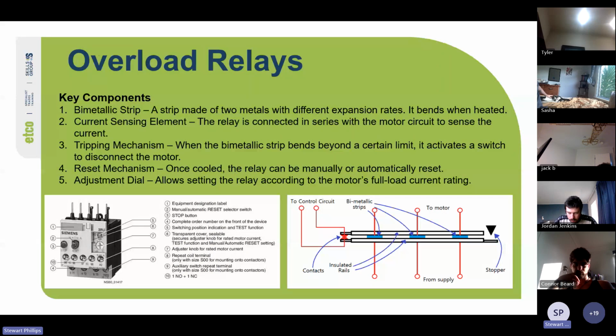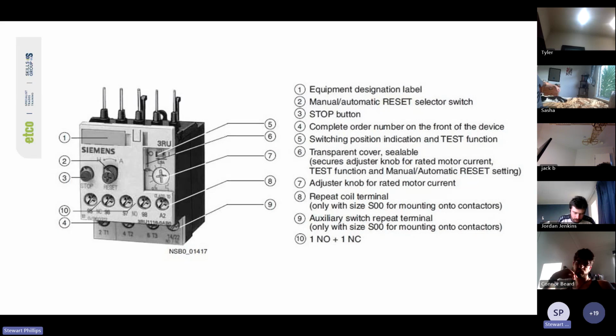And we'll take a closer look at that Siemens overload relay there. So you've got your equipment designation label, that's one that you can take out and write on a small piece of paper and put in. You've got your manual automatic reset selector switch, so it can switch between manual and automatic. 3 is a stop button, which basically just opens the thermal overload. 4, complete order number on the front of the device, so it's telling you which terminals are what. 5 is your switching position indication and test function.